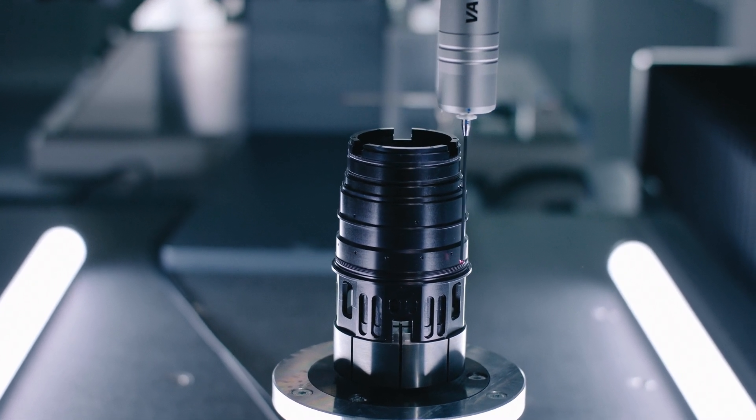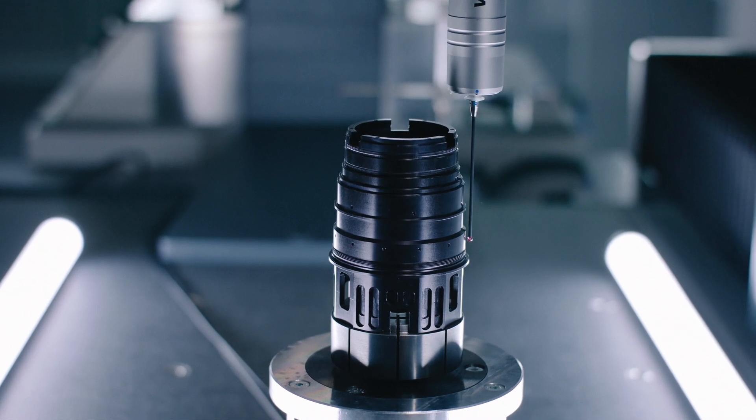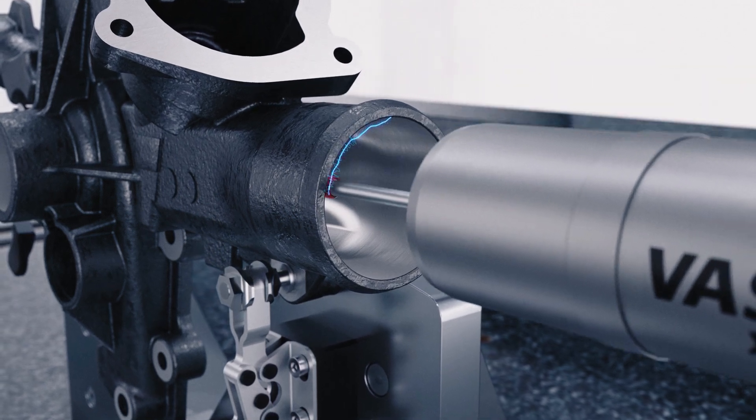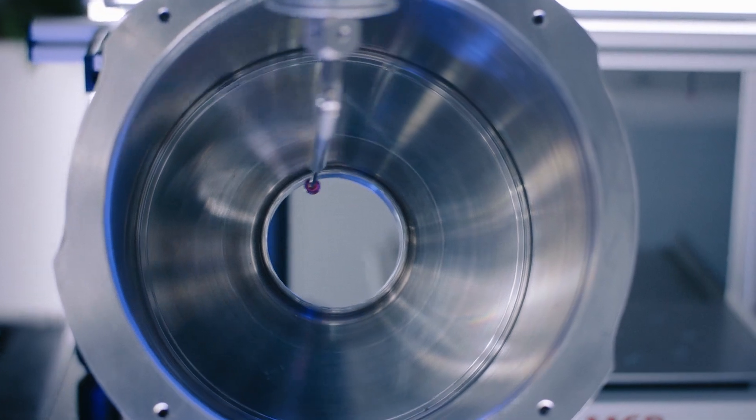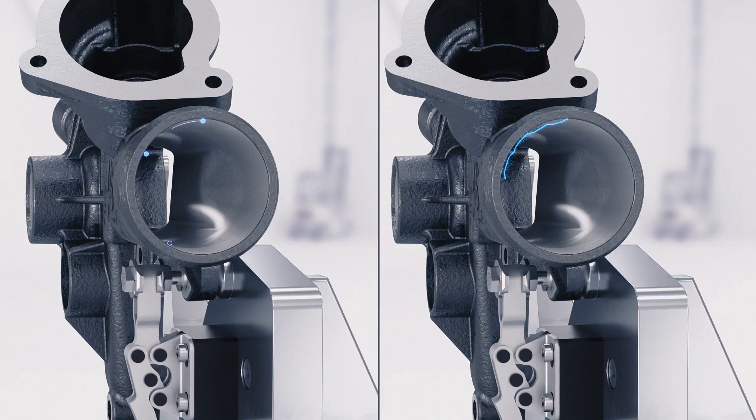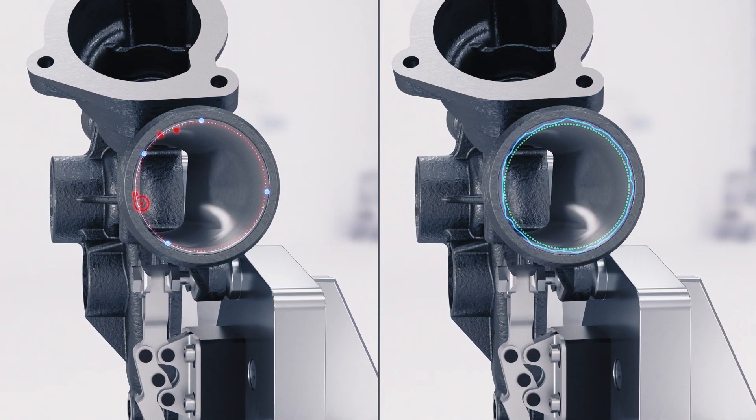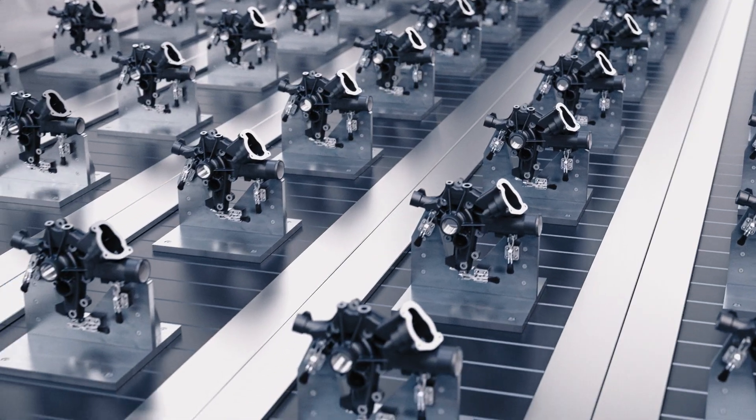With scanning measurement you get reliable and meaningful results in shorter time. The probe measures with one continuous and fluid movement resulting in a faster measurement with significantly more data and therefore better accuracy in the end.